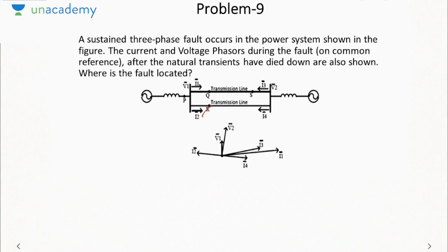Now assume that the fault is at R. Then the current will go like this. Okay. So I2 is in the same direction as shown, but just now we figured out that since I2 is leading, it must be in the opposite direction. So the fault cannot be at R. If we talk about S, then how will the current go? Like this and like this. So here if you see, the current I4 will be reversed. Okay, if we talk about S, the current I4 is reversed, but as you see, I4 must remain as it is because it is lagging the voltage. So the assumed direction or given direction is the same as the actual direction. So the last option that remains with us is Q.